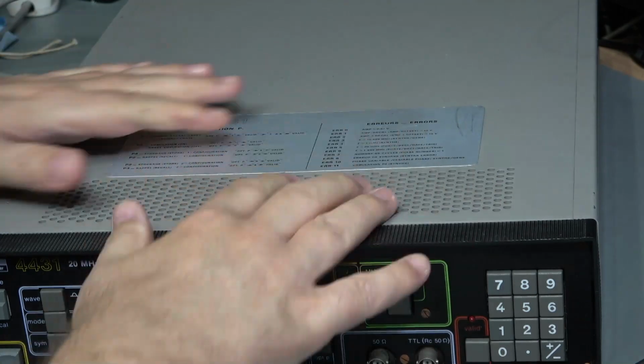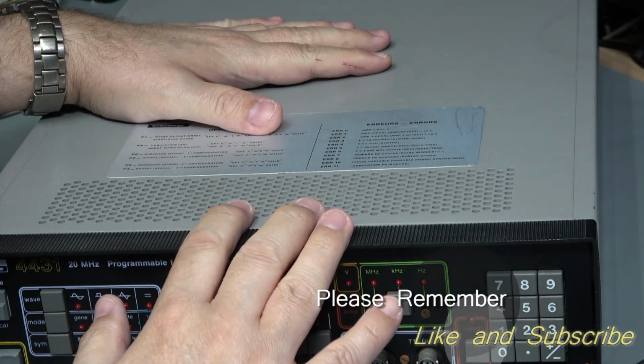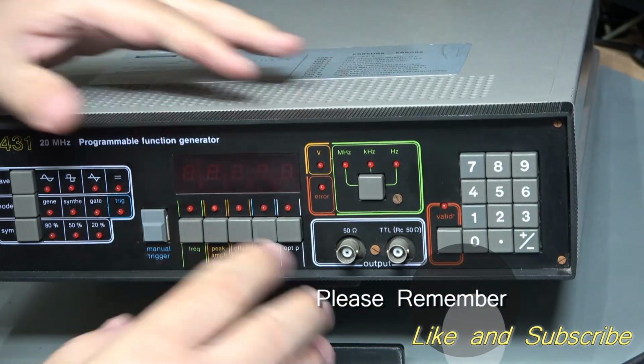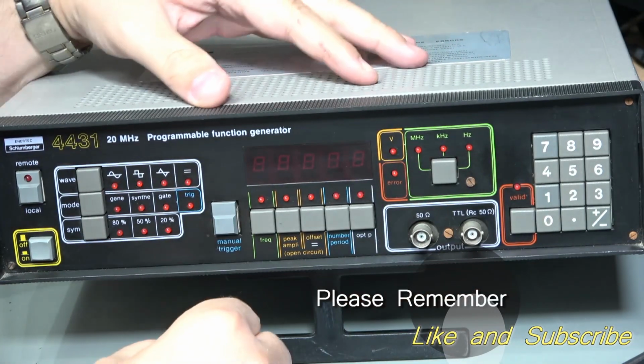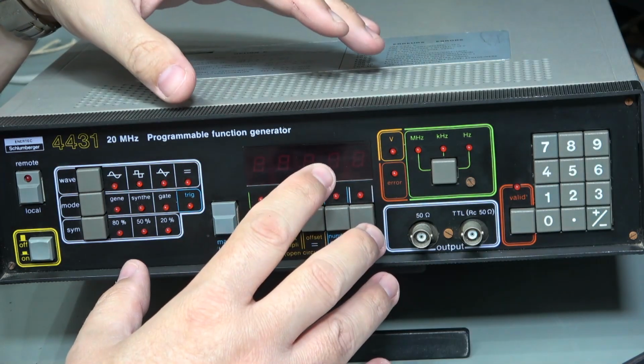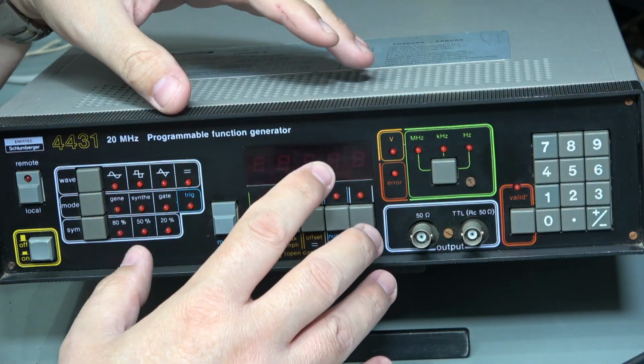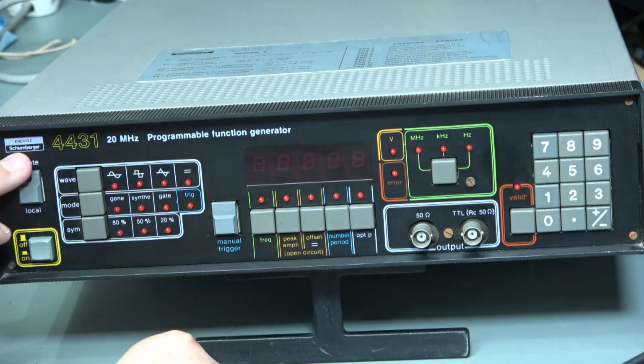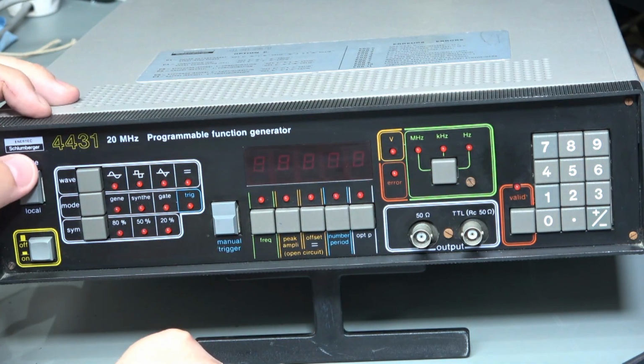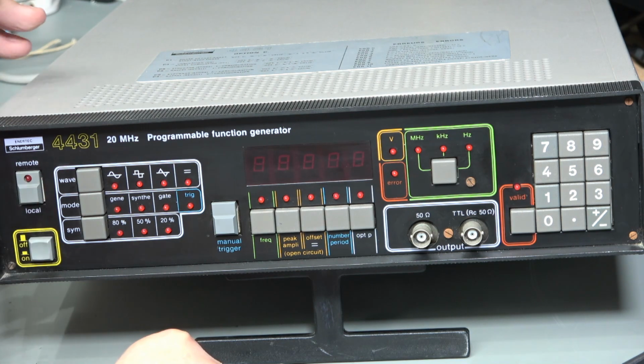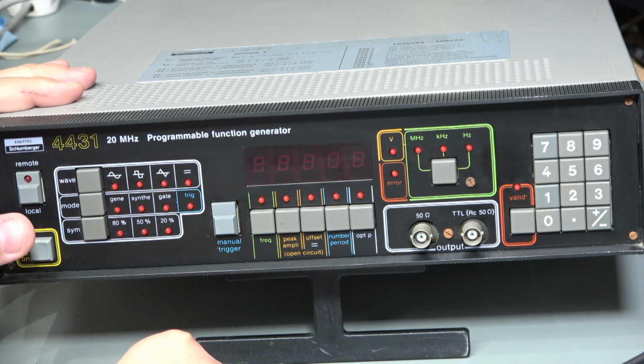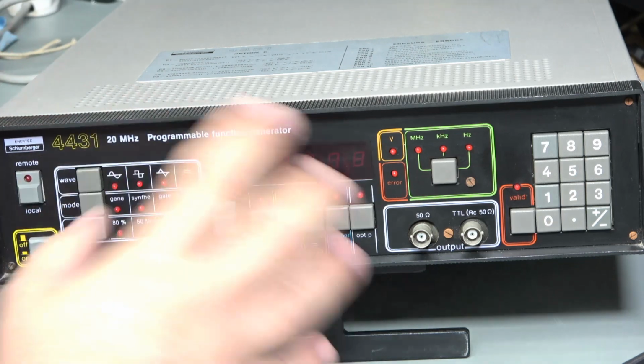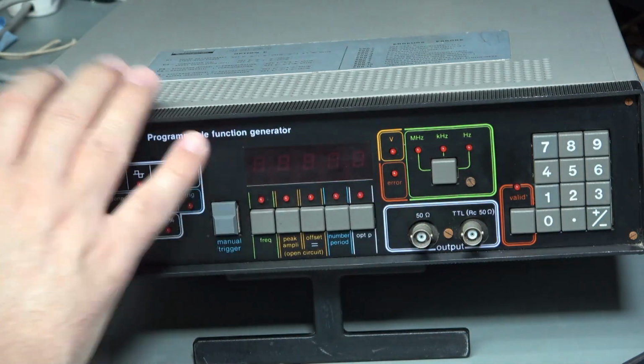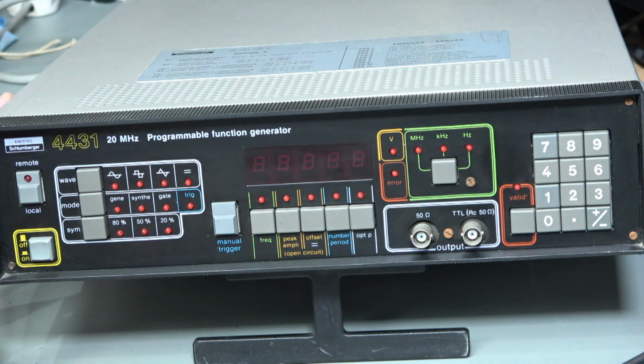Now before I move on, I am actually going to have a quick look inside, a quick look at the capacitors in particular, and I also want to see whether it's got RIFA suppression capacitors in here, because they would tend to be a bit dodgy if that is the case. I know that this company has used them before, and it's also used some Schaffner input suppression, which hasn't been very reliable before on some other models. So I don't know quite what this one's got in it at the moment, but I want to just take a look and make sure that everything looks good before I power it up for very long.